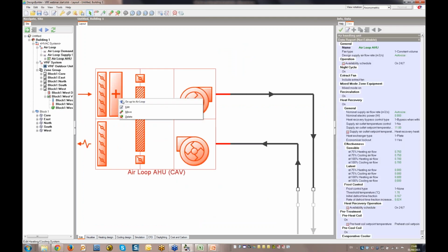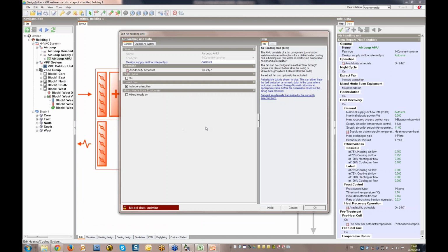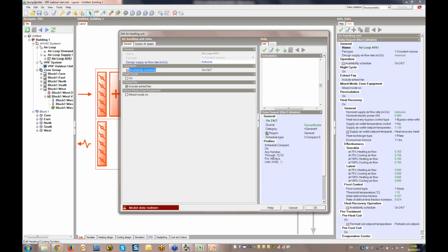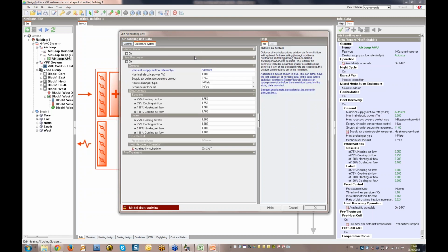Going to the AHU edit dialog, in the General tab, I can schedule the AHU. Here I'll set it to operate from 7 AM to 6 PM Monday to Friday only. Here in the Outdoor Air tab, I could specify parameters such as an airside economizer, but clearly that's not relevant to a DOAS system, which is only sized to meet the ventilation requirement. Most of the options here relate to the heat recovery system, which I'll leave at default.